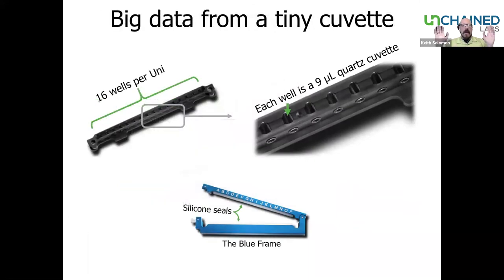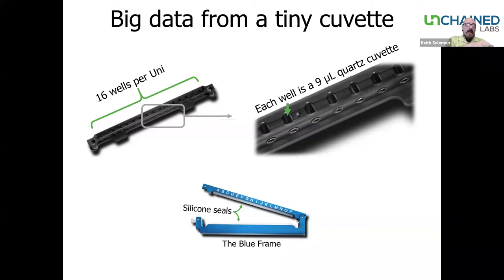One of the things that makes the UNCLE such a powerful instrument is the design of a proprietary sample holder called the UNI — an array of 16 optical-grade quartz cuvettes in an anodized metal frame. Each cuvette takes exactly 8.8 microliters and is open on the top and bottom so any gas evolves to the surface and disappears. Once filled, they're sealed between silicone gaskets, allowing long-term stress analyses up to three months. The UNI sits right on top of the Peltier element, allowing efficient heat transfer during thermal ramps.